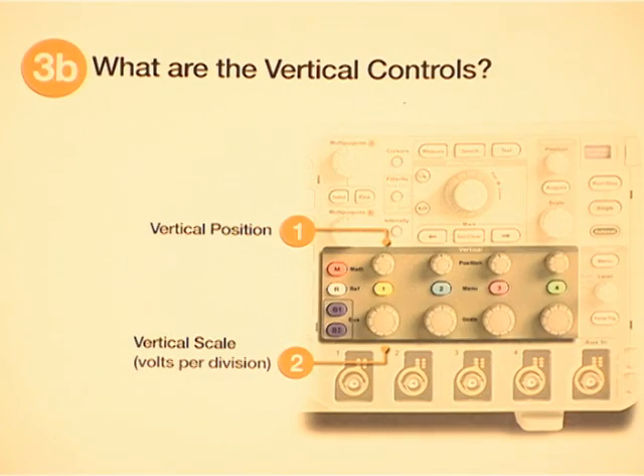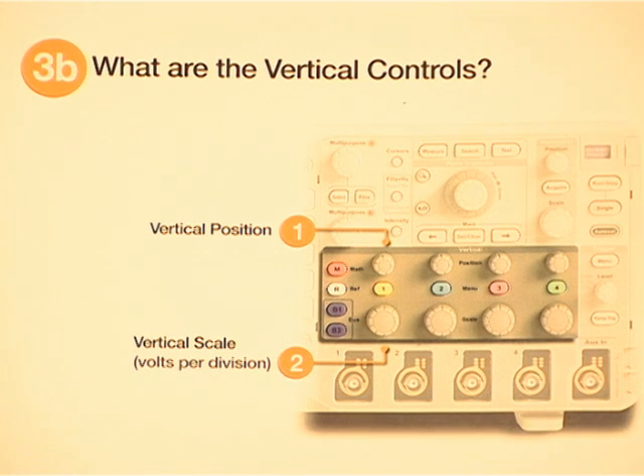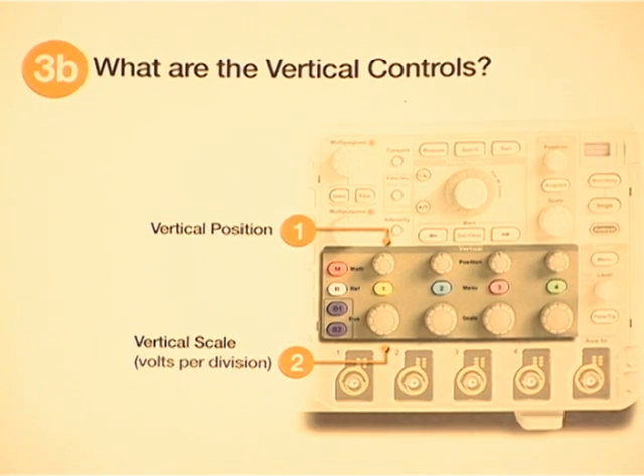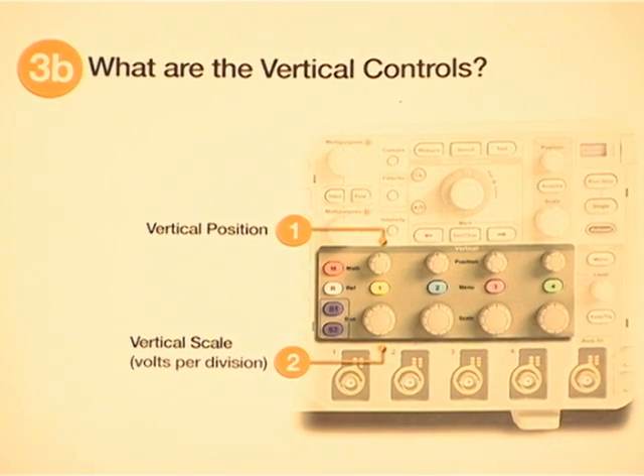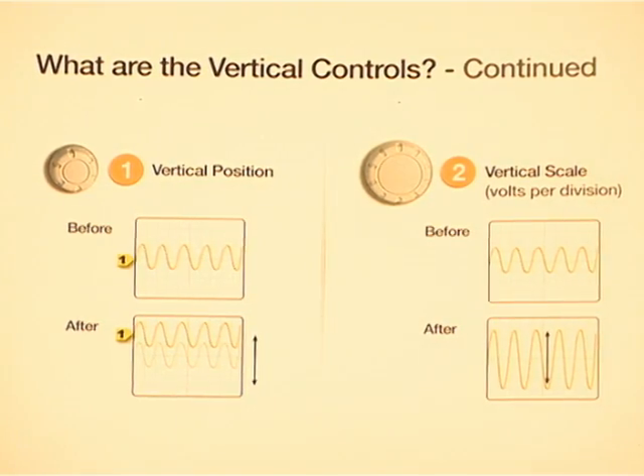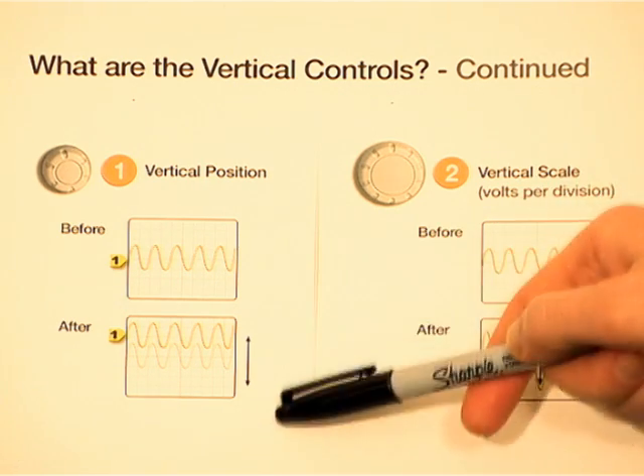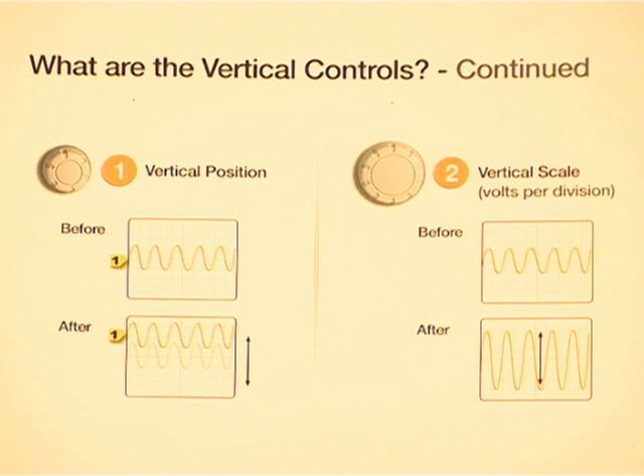So this particular scope can display up to four analog channels from different inputs. And each channel has its own independent set of vertical controls. That means each waveform can be positioned independently of the others on the screen. And the two most important vertical controls are the vertical position and the vertical scale. So the vertical position moves the waveform up and down the screen. And the vertical scale expands or compresses the waveform vertically.